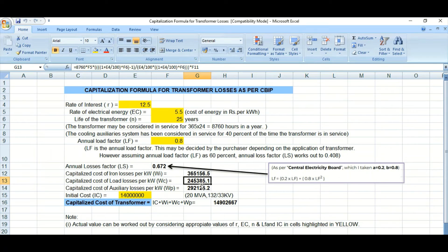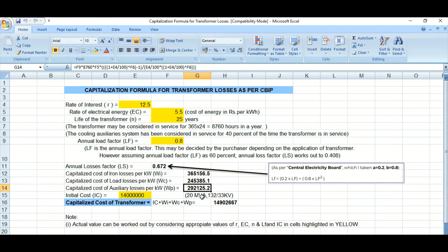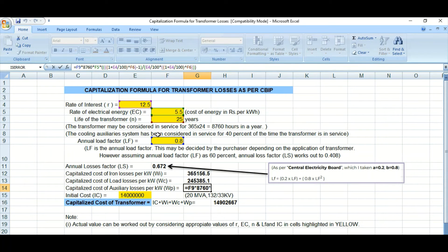For the auxiliary losses, the capitalized cost per kilowatt uses the load factor multiplied by 8760 and the electrical energy rate. This formula derives the auxiliary loss capitalized cost, denoted as WP.